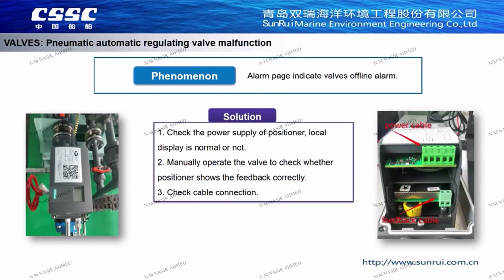Pneumatic control valve failure. If the system issues a valve offline alarm, check the local position of the power supply. If no power, check the power cable from the system cabinet. Manually open and close the valve and observe whether the display position of the positioner is correct. If the feedback is correct, check the feedback cable circuit. If it is incorrect, it is a fault of the feedback circuit board of the positioner.